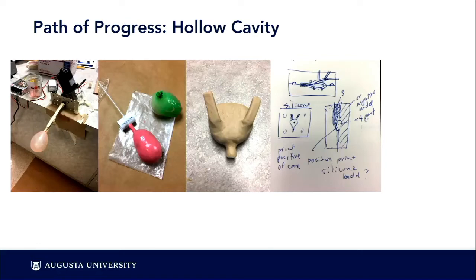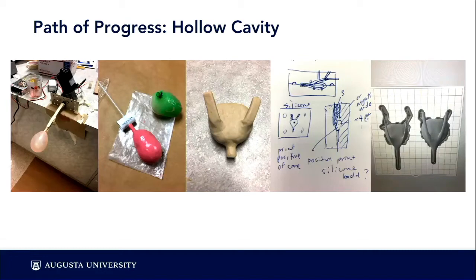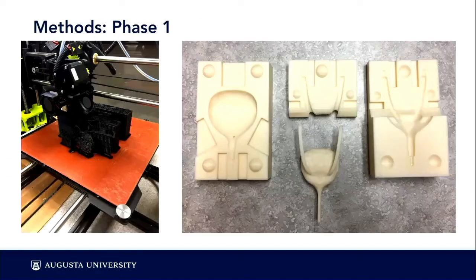We took the 3D scan, made modifications to client specifications, then 3D printed both the positive shape and the negative shape that would create the core. They wanted to see anatomical features inside the bladder, and by 3D printing both parts they were able to review and provide feedback on the ureteral orifices and fidelity. We made a four-part mold where the core was suspended inside to cast two layers of silicone — one a muscularis layer — creating a double-layer model.